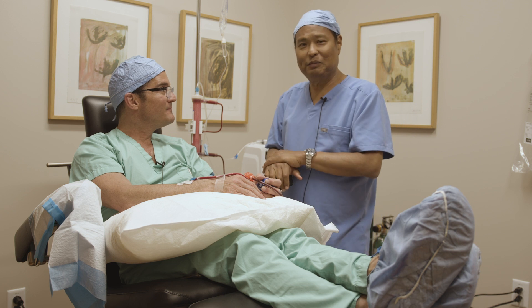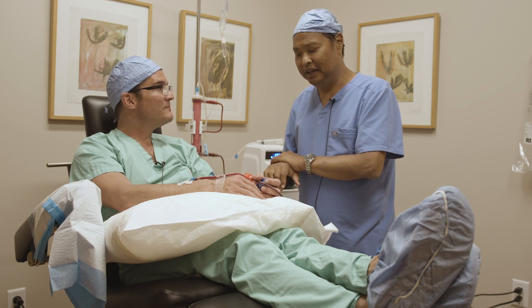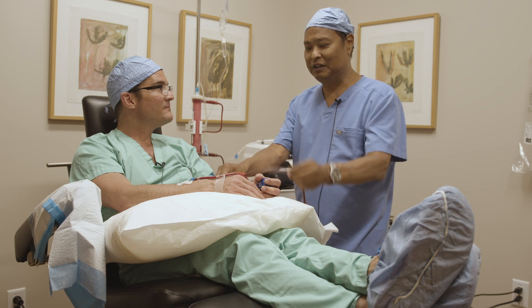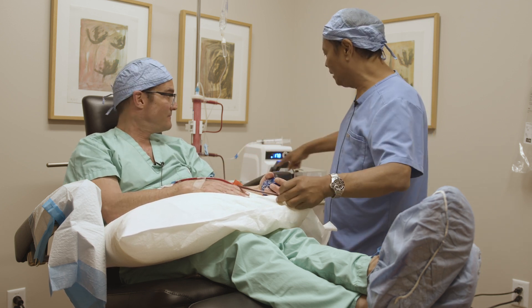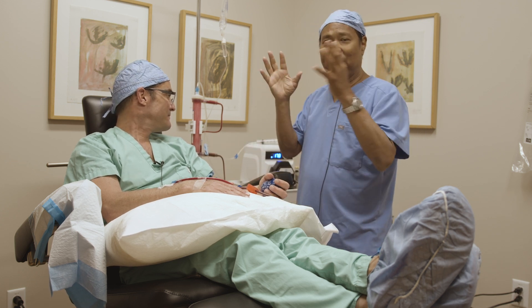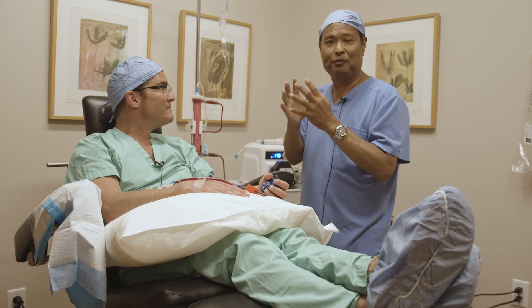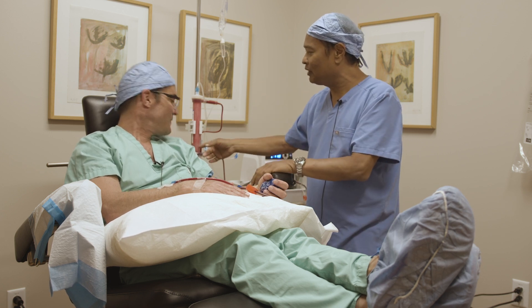The EBO2 system is a very simple system — it's a modified dialysis system. What we're doing is taking blood from our patient, running it through our pumping mechanism into our filter. The filter then grabs all the fat, proteins, and waste products, and we filter that out of the blood, separate it out through our specific membrane.